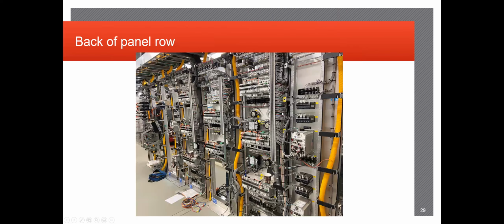It's an example right here of what the back of some of these panels look like. This is fairly interesting. I guess this client has an open design cabinet layout, which I'm not the biggest fan of, because I feel like there's a lot of room for human error, especially if there are site visits or any sort of maintenance testing. There are a lot of bits and ends sticking out. If a wire wasn't screwed in properly and you kicked this bundle right here and that wire got pulled out, you could initiate a trip, you could cause all kinds of issues.